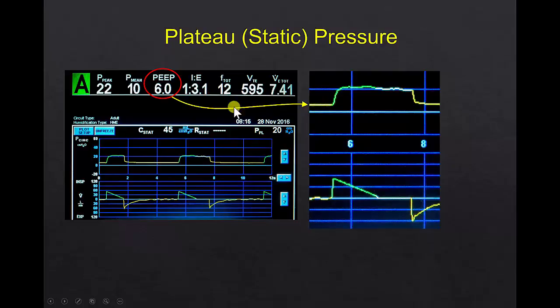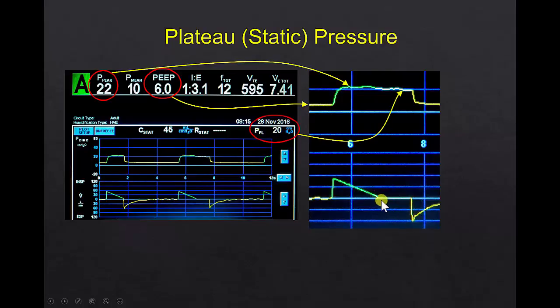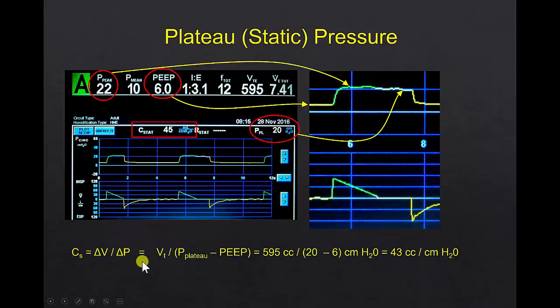The PEEP was 6 and the peak pressure was 22 — the pressure required to both stretch the lung to 600 cc's and deliver the flow. During the plateau maneuver, flow is zero, so all pressure across the resistance dissipates, and the remaining pressure is the plateau pressure — in this case 20 — which is the stretching pressure used in compliance calculations. To calculate compliance: tidal volume of 595 cc's divided by the pressure change from PEEP of 6 up to plateau of 20, which is 14, gives a compliance of 43 cc's per centimeter of water.